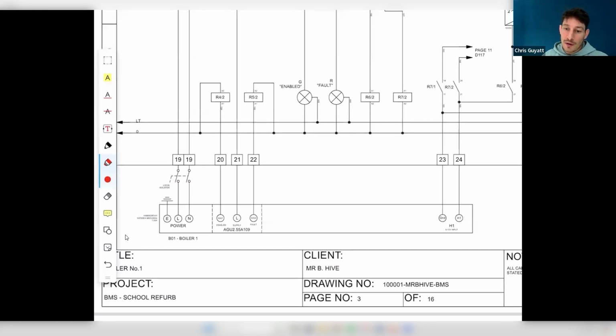And typically the way to do that on boilers is an analog signal - a range, so 0 to 10 volts or 4 to 20 milliamp, are typically the analog control signals used. In this case, the boiler has that additional module that we need to clip into it.